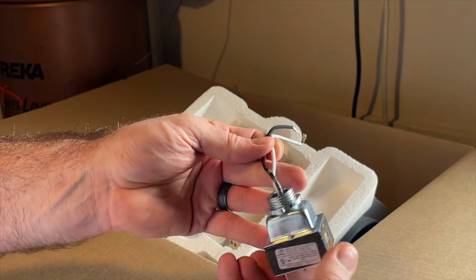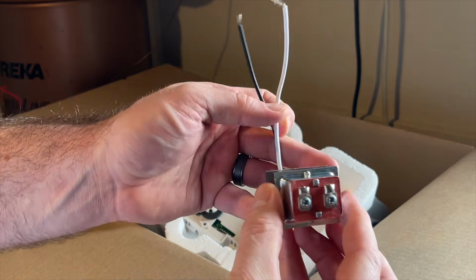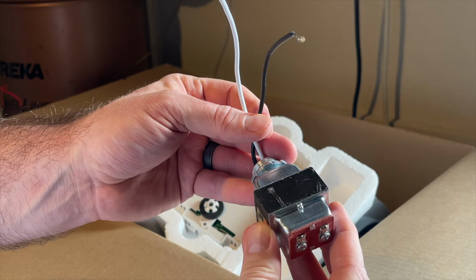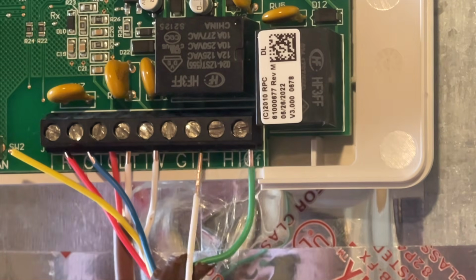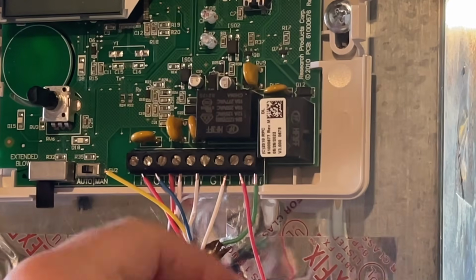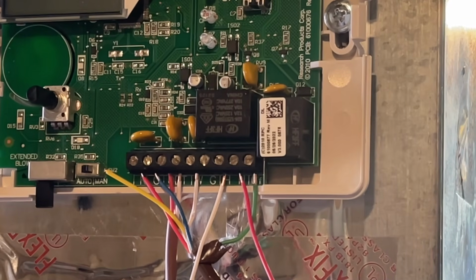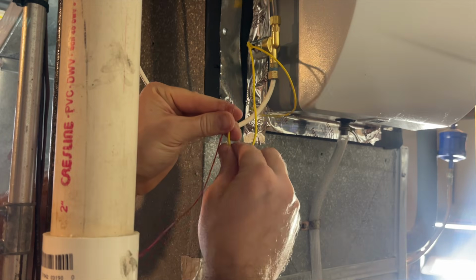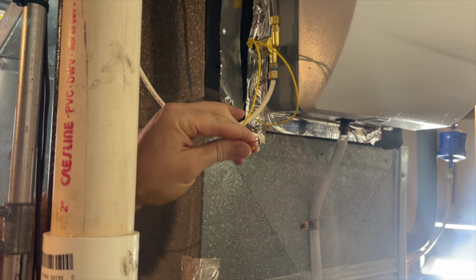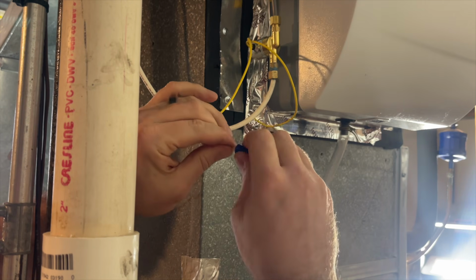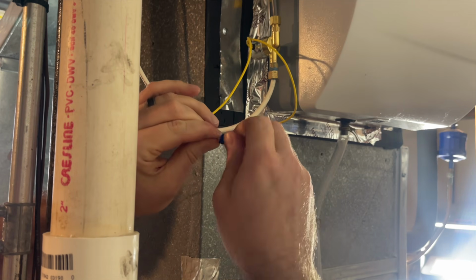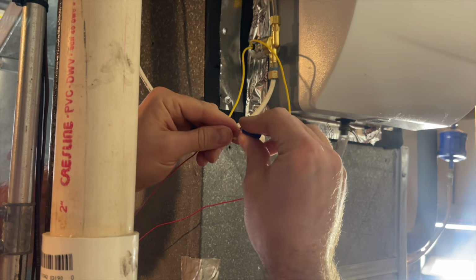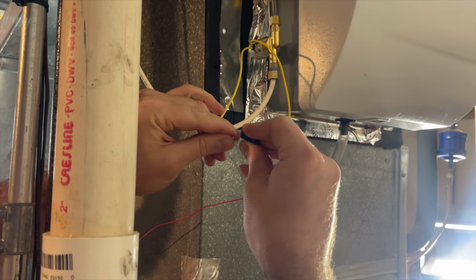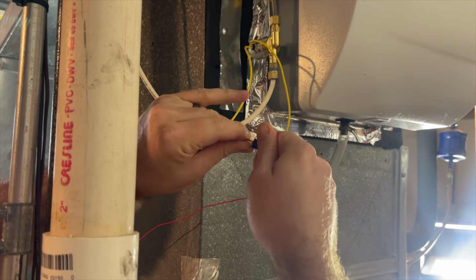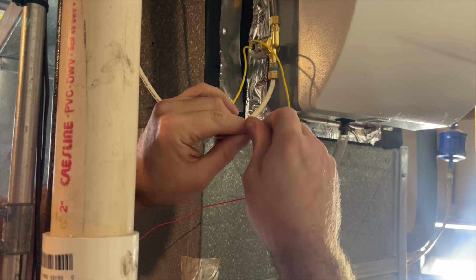Next, we're going to connect the transformer, which brings power to the humidistat and the humidifier, using the cable with 2 wires, hooking the white wire to the left H and the red wire to the right H. After peeling the cable apart, we connect the red H wire to one of the yellow wires attached to the humidifier. Next, we're going to add another portion of red wire to the other wire attached to the humidifier, but this one's going to run down to the transformer.